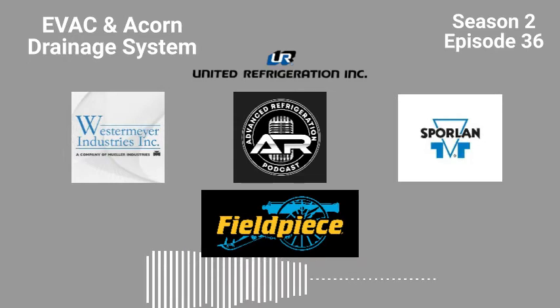Yeah, generally I find them tripped after power surges out here. I think it's the number one call for power surges out here, especially like the Aldi. It's tripped EVAC contactors. I make sure guys check them every single time now there's a power outage. I want them to open up the EVAC panel, because generally it'll be one of the two that are tripped, and then you end up getting an EVAC alarm randomly right after you leave. You want to make sure that thing is not tripped on one of the pumps.